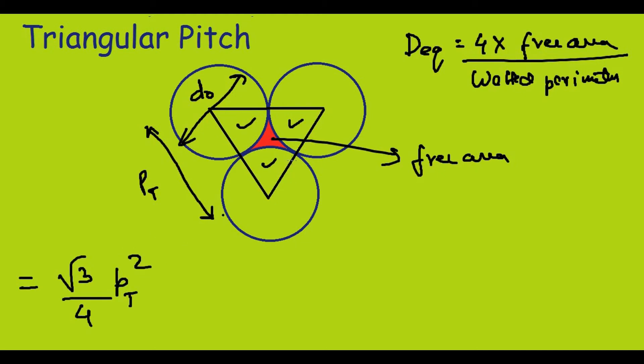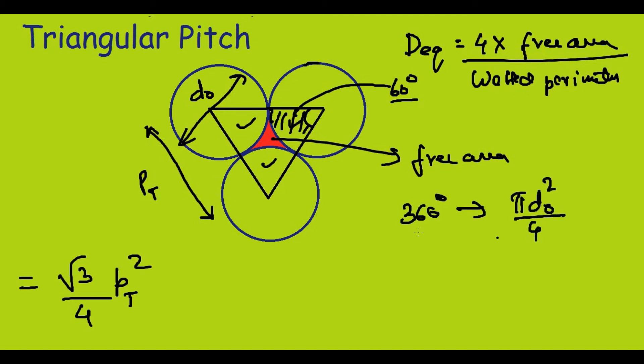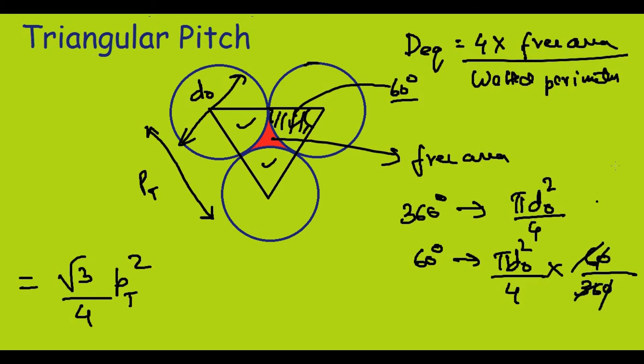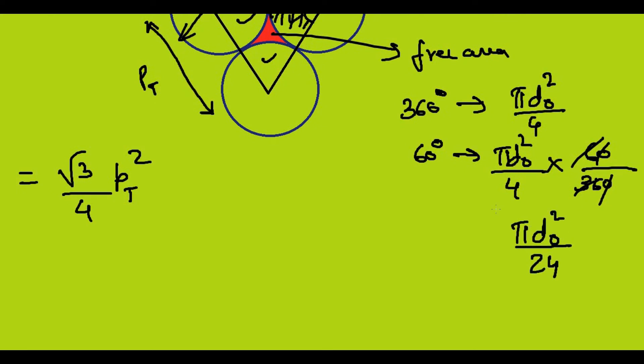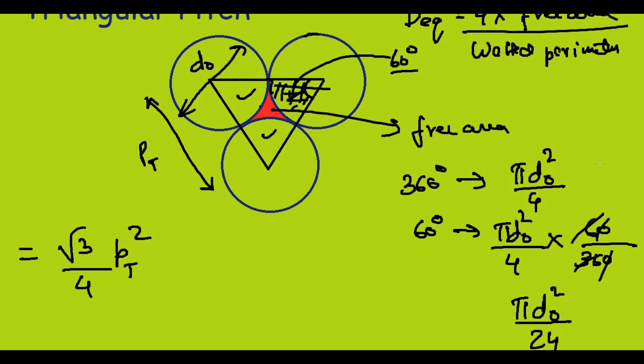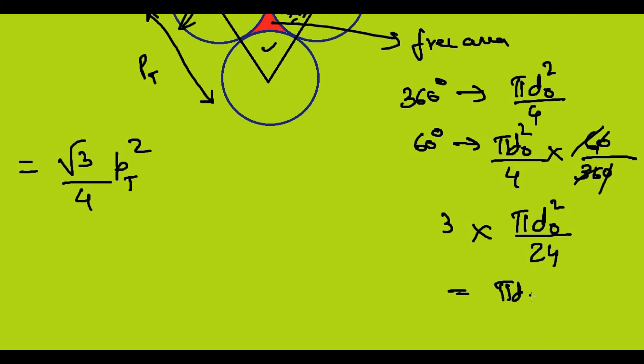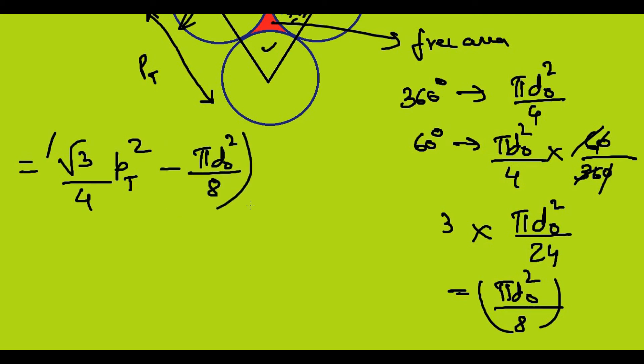Since this is an equilateral triangle, each angle is 60 degrees. To find the area of each circular sector at the corners, for a full 360 degrees the circle area is πDO²/4, so for 60 degrees it is πDO²/4 × (60/360) = πDO²/24. I have 3 of these pieces, so multiplying by 3 gives πDO²/8. The free area is therefore (√3/4)Pt² − πDO²/8.